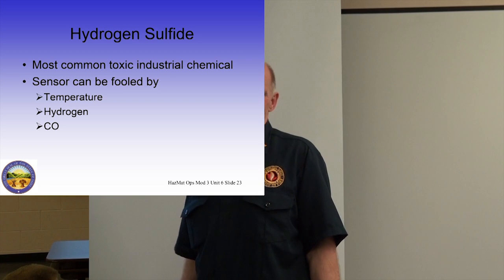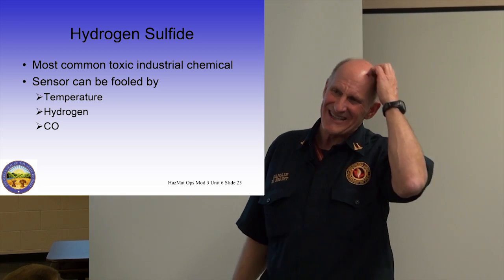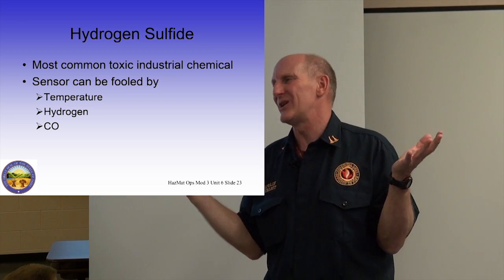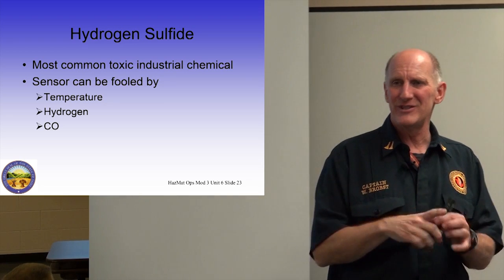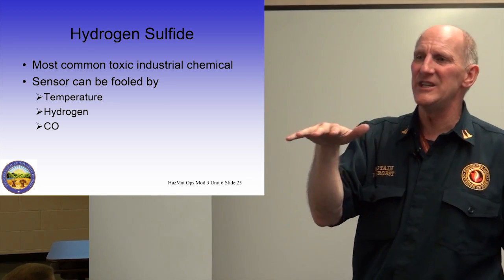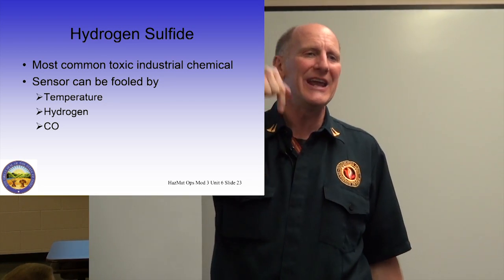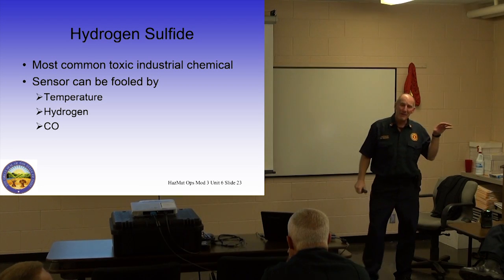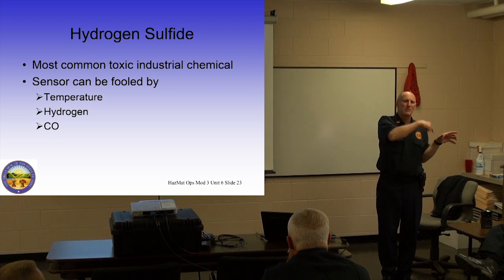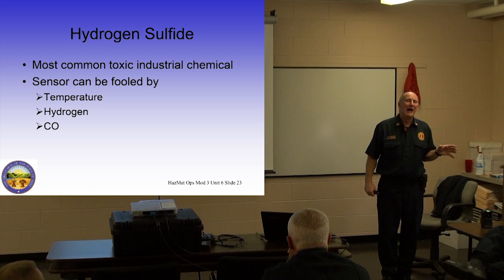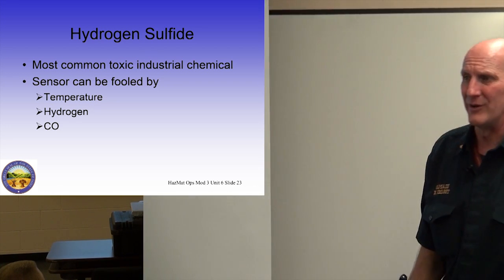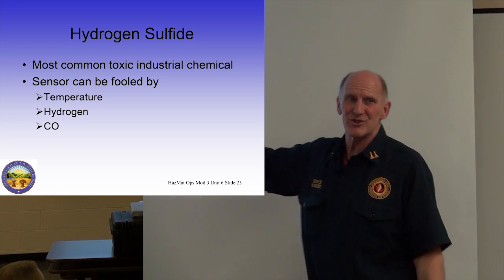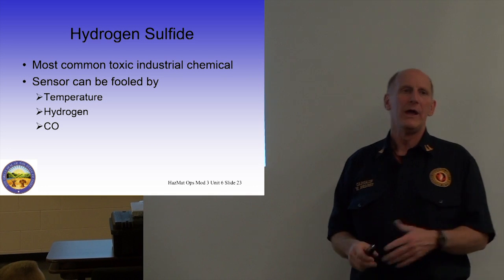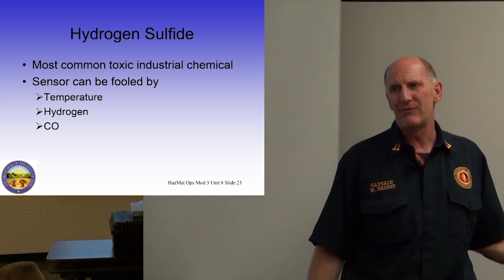The hydrogen sulfide and carbon monoxide sensors are nearly identical to each other. The only difference is there's a little membrane on the CO sensor that's not supposed to let H2S in, and a little membrane on the H2S sensor that's not supposed to allow CO in. But they're not 100% accurate. So even the presence of hydrogen sulfide may fool the CO sensor, and you may also get a reading of carbon monoxide.